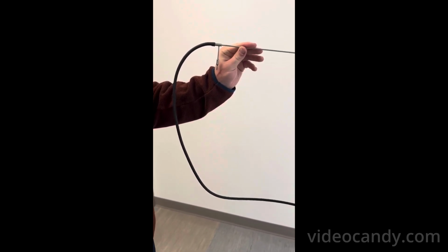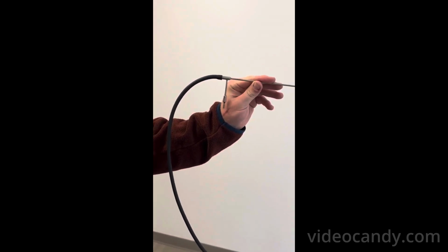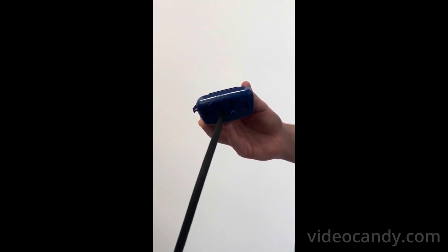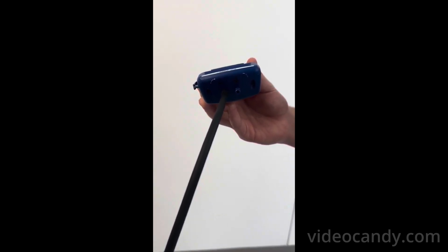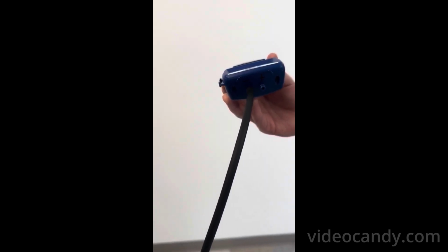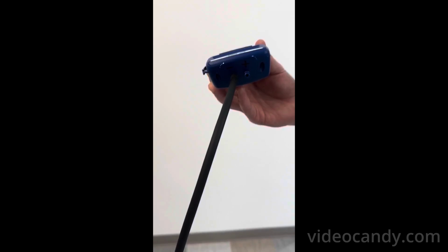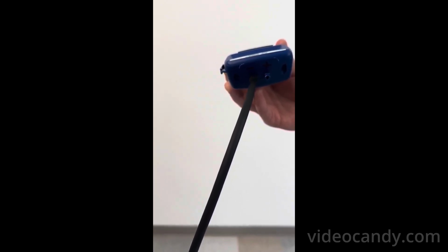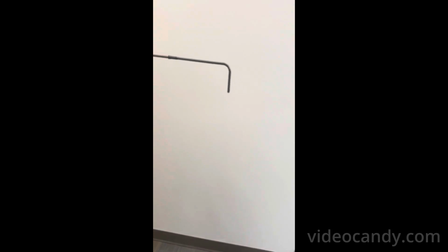Finally, to measure total pressure, you're going to have one tube connected to the inside pitot tube measurement. Remember that total pressure is negative before the fan, and so instead of having the inside tubing connected to the positive terminal, you're going to want it to be connected to the negative terminal. Once your device is set up like this, you can plug the terminal end into the fan and take your total pressure measurement.